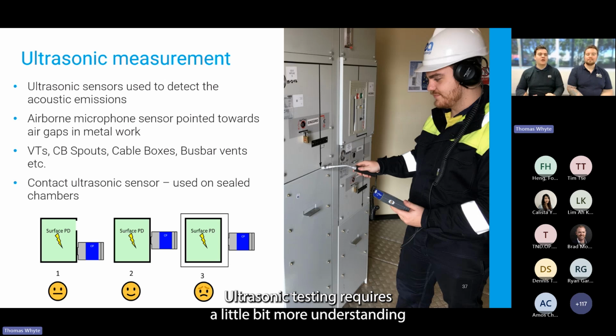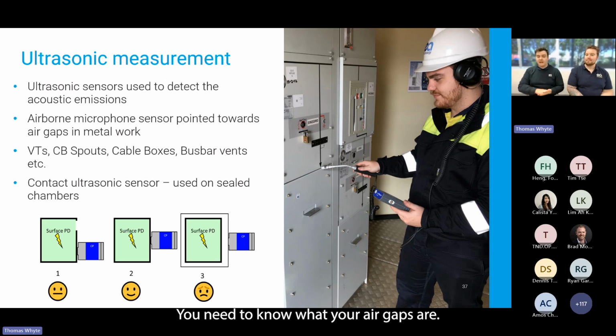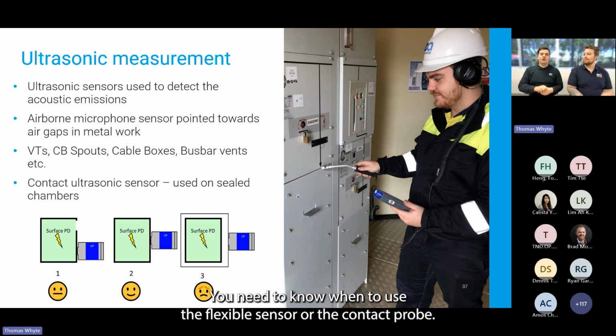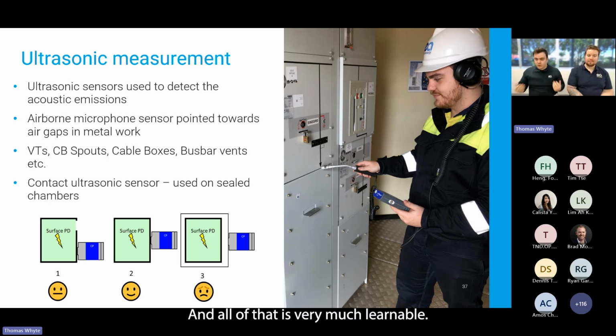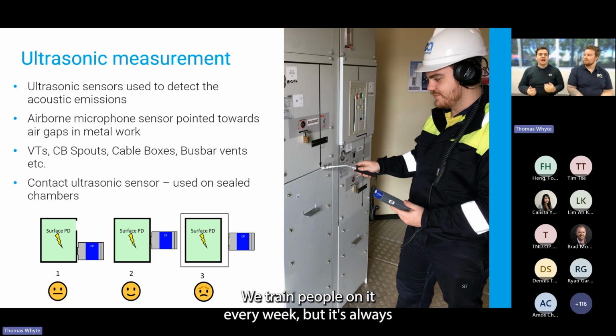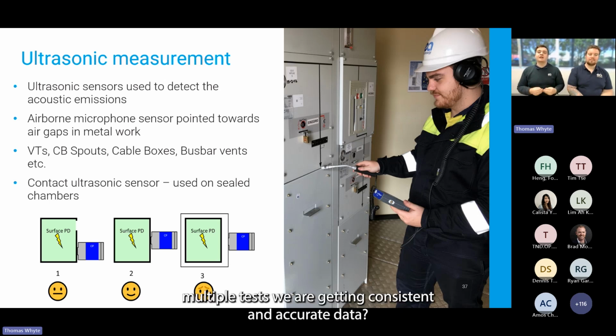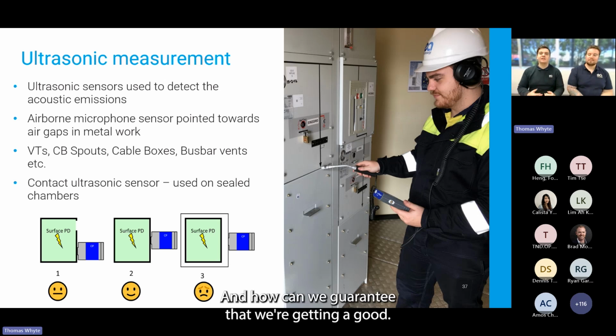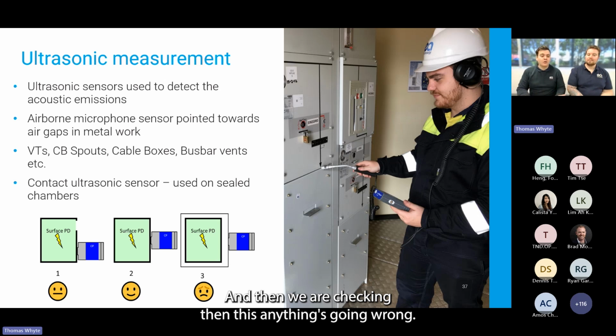Ultrasonic testing requires a little more understanding about your assets and the design of the switchboard. You need to know what your air gaps are, when to test, and when to use the flexible sensor or the contact probe. All of that is very much learnable, and we train people on it every week, but it's always been a bit of a contentious point: how do we trend it, how do we make sure that between multiple tests we're getting consistent and accurate data, and how can we guarantee we're getting a good air path and checking that nothing's going wrong?